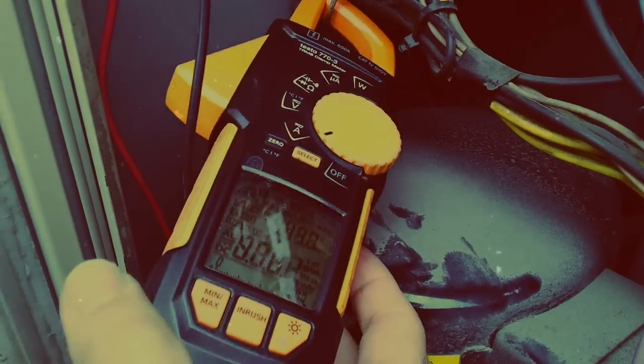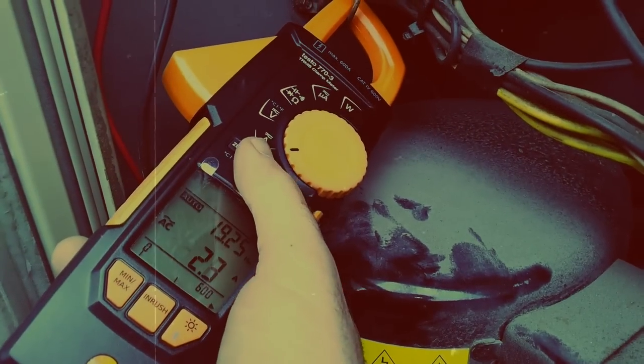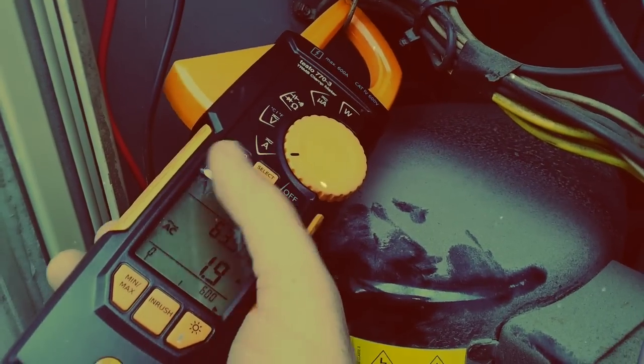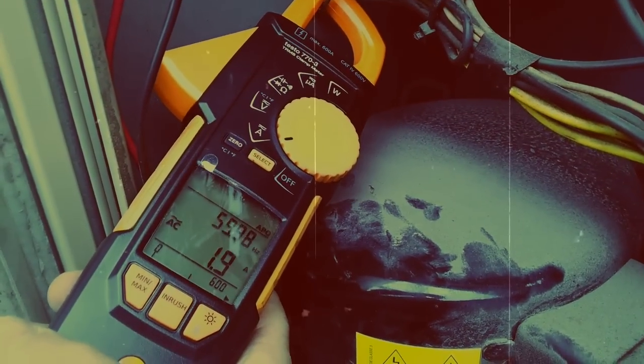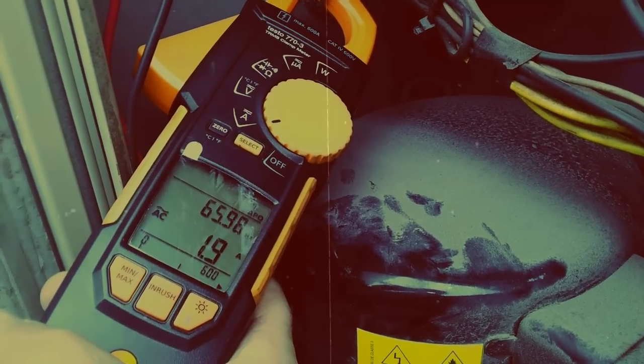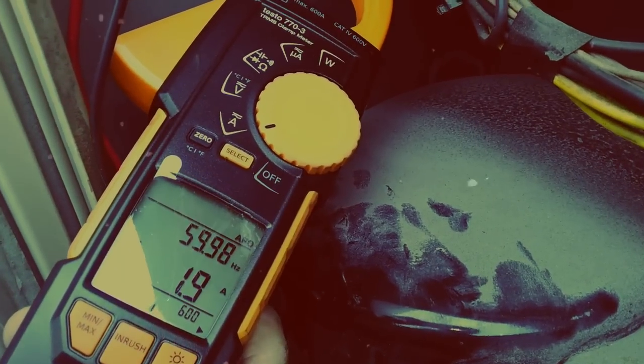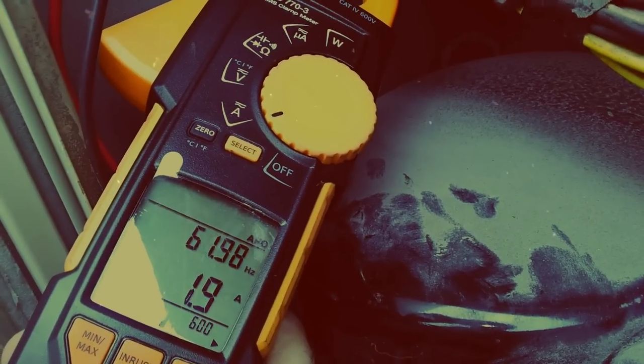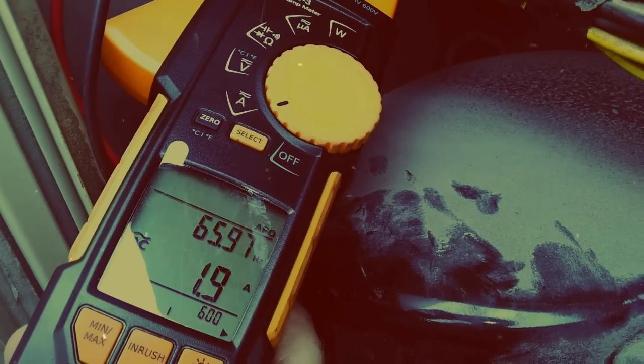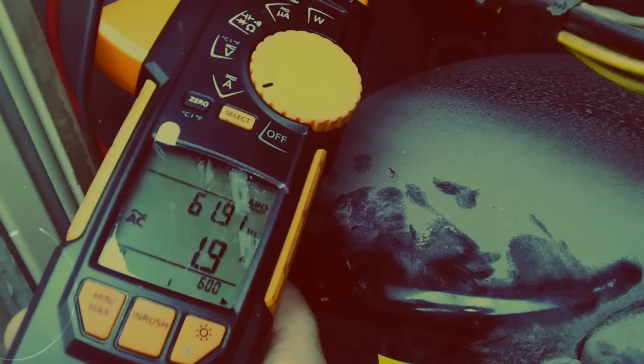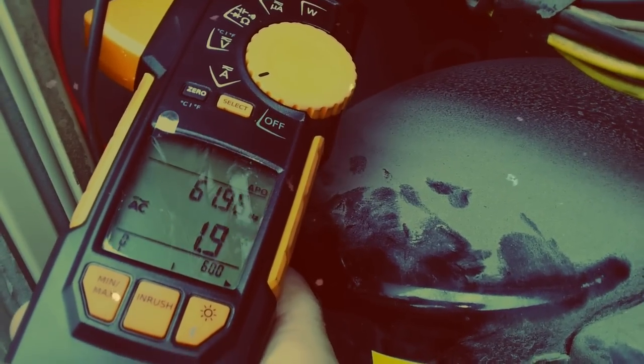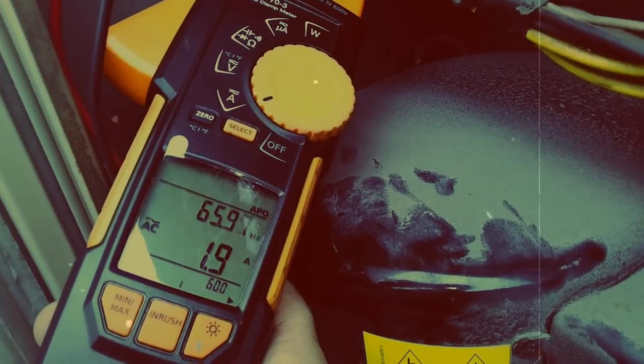We're going to set the meter to amps, and we're going to read our amperage at AC 1.9. And as you can see above it, there's a handy feature to have. We're reading the frequency of the motor. You can see it jumping around a little bit, but reading the frequency in hertz, different applications can come in real handy.